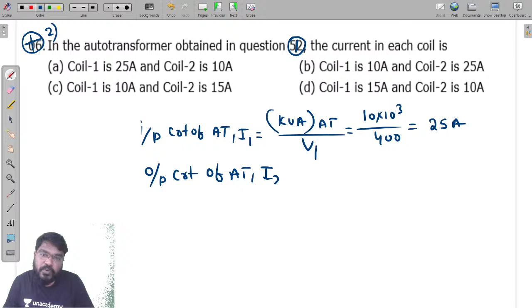Now the output current of the auto transformer, that is I2. How do we get I2? kVA rating of the auto transformer divided by V2. So here 10 into 10 to the power of 3 divided by 1000, that is equal to 10 amps of current.